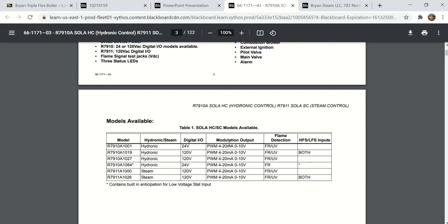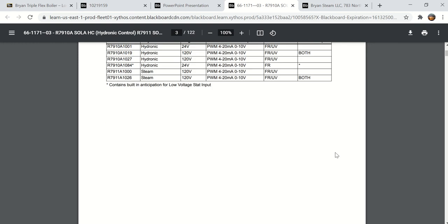Modulation outputs, these are 3 different distinct types of modulation signals. Pulse width modulation is one type, 4 to 20 milliamp is another type, and 0 to 10 volt is another type. So when you see this, I don't think they separate them the way they should, but these are 3 separate types of modulation signals. You can have 2 different types of flame detection, either a flame rod or an ultraviolet scanner. The flame rod, probably more typical on residential and light commercial kind of equipment, where you just have a rod, and that rod uses the flame and the ability to pass current through the flame to detect there's flame present. The ultraviolet does it by radiation, ultraviolet radiation of a combustible flame. That's how it knows there's a flame present.